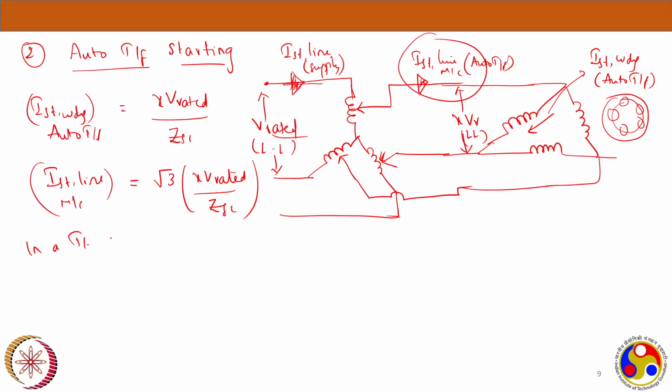How to calculate this primary current? In a transformer, input kVA will always be equal to output kVA. Transformer kVA is constant. You can't change it. A 5 kVA transformer is 5 kVA in input and output. You need to calculate voltage and current in the input, and voltage and current in the output. You will have the same kVA.